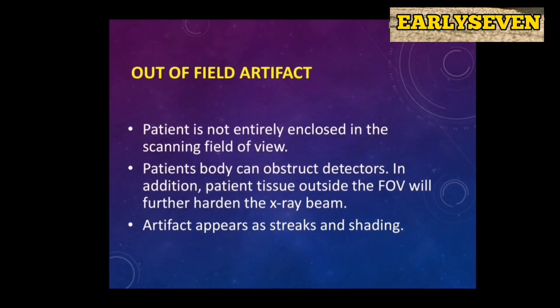Another artifact is the out-of-field artifact. This happens when the patient is not entirely enclosed in the scanning field of view, or FOV. The patient's body can obstruct the detectors. In addition, patient tissue outside the FOV will further harden the X-ray beam. The artifact appears as streak or shading.